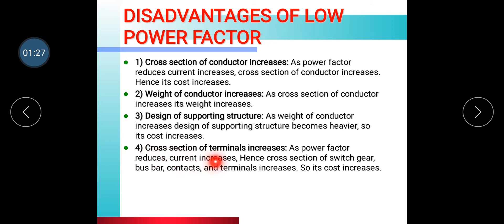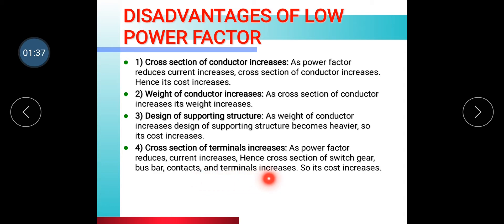Next, the cross section of terminals increases. As power factor reduces, current increases, hence the cross section of switchgear, bus bar, contacts, and terminals increases. As the power factor reduces and current increases, the cost of these components also increases.